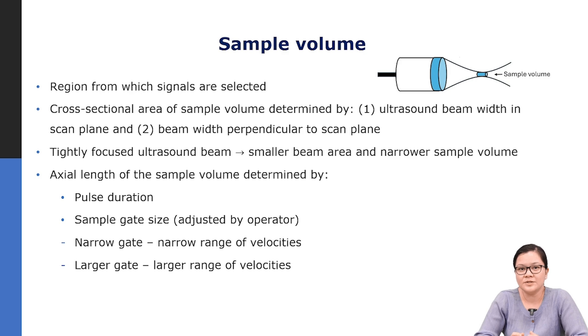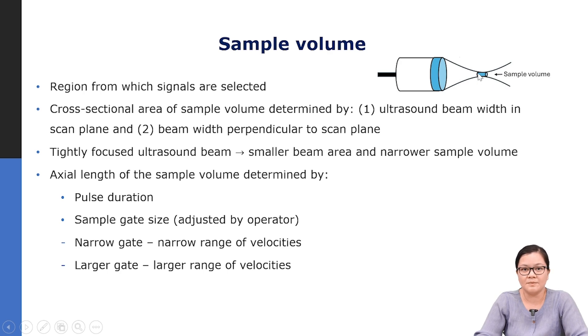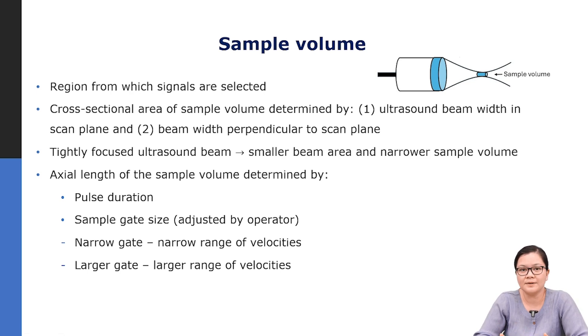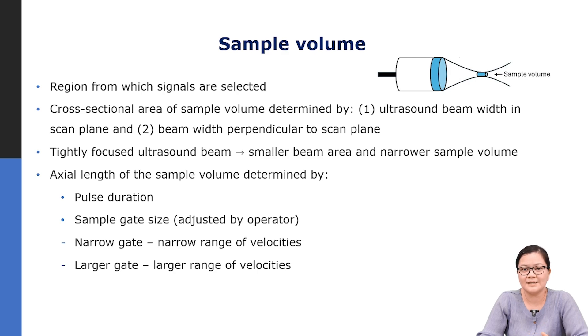The region from which signals are selected is called the sample volume. The cross-sectional area of the sample volume is determined by the ultrasound beam width along the scan plane and perpendicular to it — a tightly focused beam gives a narrower sample volume. The axial length of the sample volume is determined by the pulse duration and the gate size selected by the operator. A narrow gate images a narrower range of velocities; a larger gate samples a larger range of velocities in the blood.